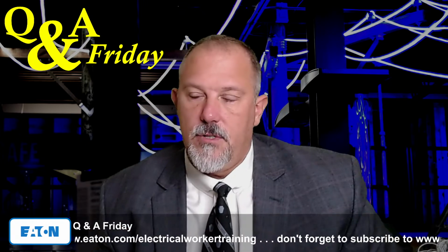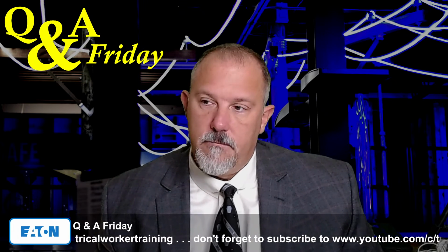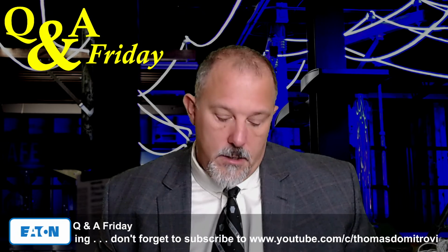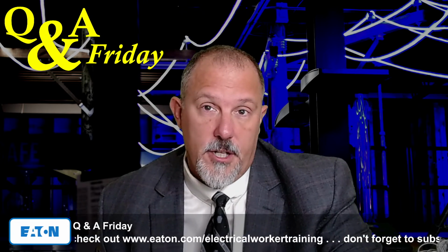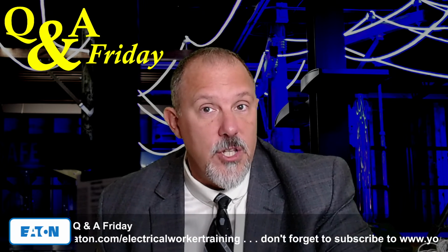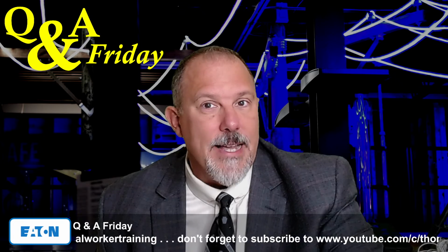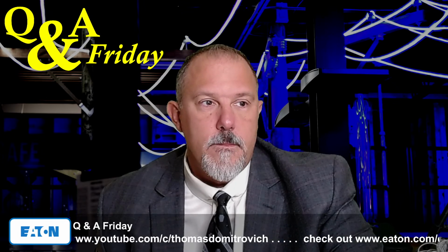So what they're talking about is that, for example, if I'm using a fuse to do arc energy reduction, I wouldn't want to throw my current through there, watch the fuse open, and then go buy another one. Although I'd love for you to do that, it's not required. If I have an arc quenching technology that looks at light, and current is not the primary method, a light source is, I could inject current and have it go off and then have to replace the arc quencher because I've damaged it. But I haven't really tested it because I need to do the light, etc. I haven't fully tested all of the capabilities of the device.